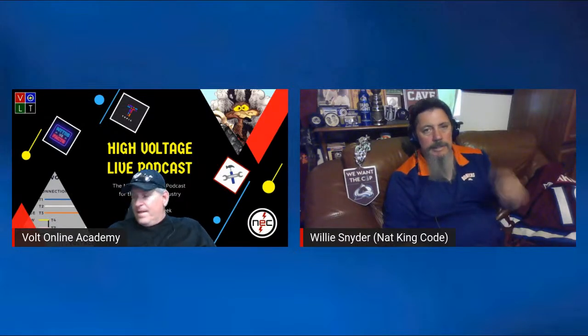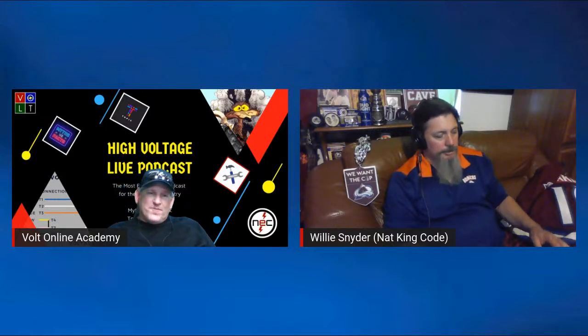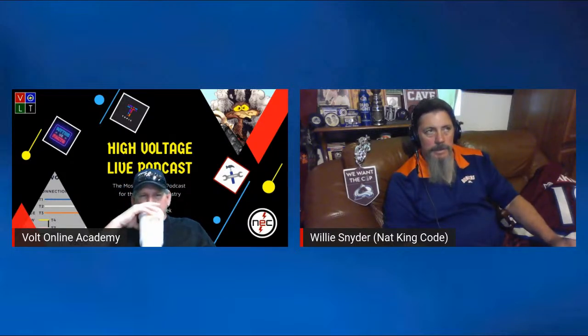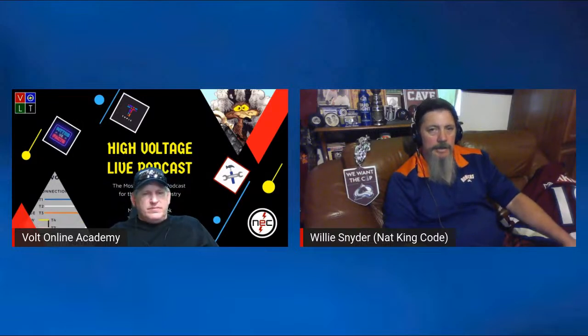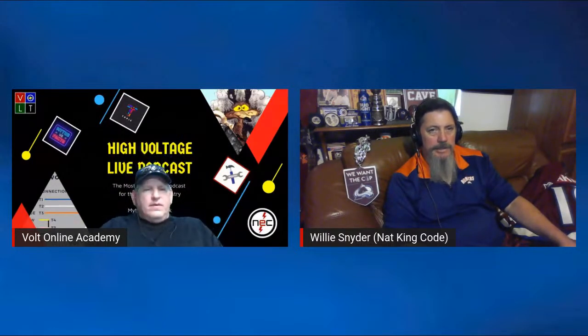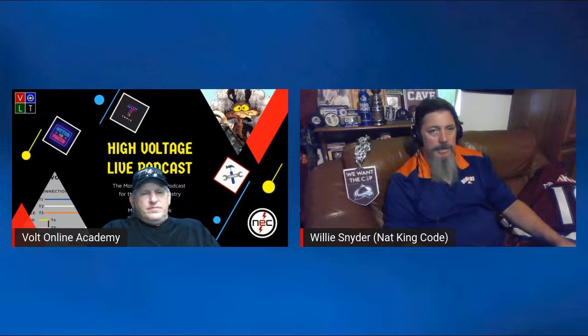I won't disappoint anybody - I'll make sure I got some good pictures from the field. This has come up before, where we have VAV units in the ceiling, and it's almost impossible for these units to have a 3-foot working clearance. I've seen multiple times where there's no way you're getting 3 foot up there, and on top of that you've got 3 foot to, say, a concrete wall.